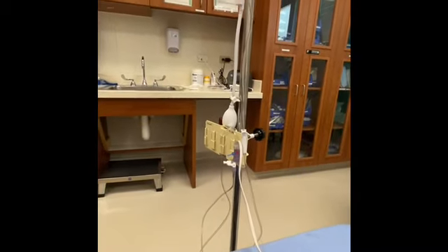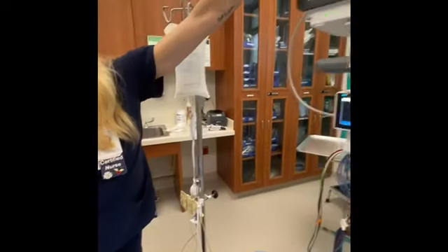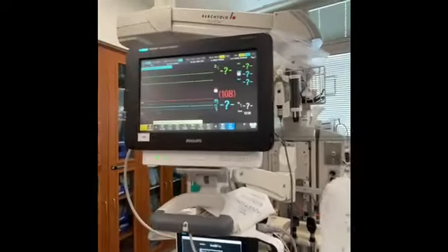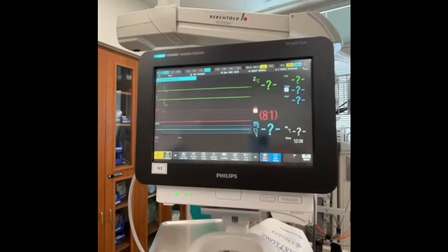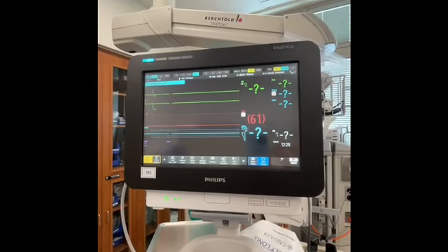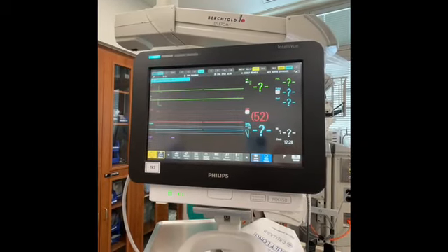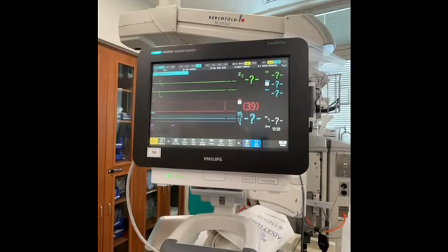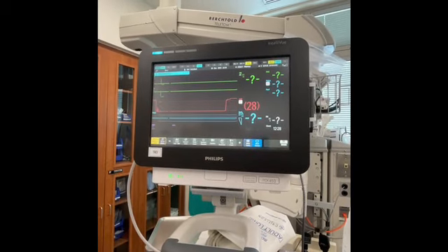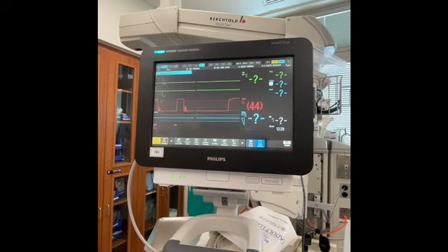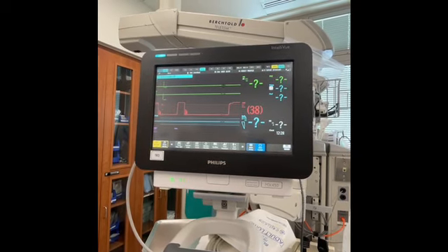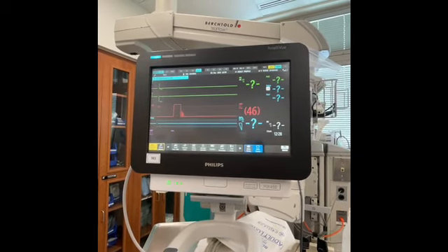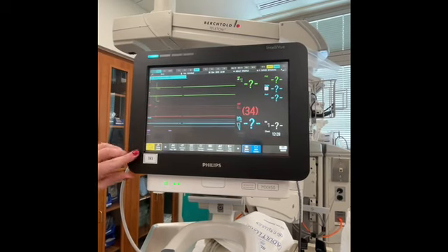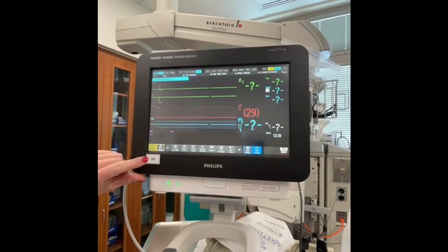Now, with the monitor, this obviously is not connected to a patient, so we're not getting any waveforms, but you can do a fast flush test and it will still work. So you're going to pull that fast flush device, which is that blue tab, and you should see a waveform. That's called a fast flush test, and we can talk a little bit more about that at a later time. A few tricks with the art line.